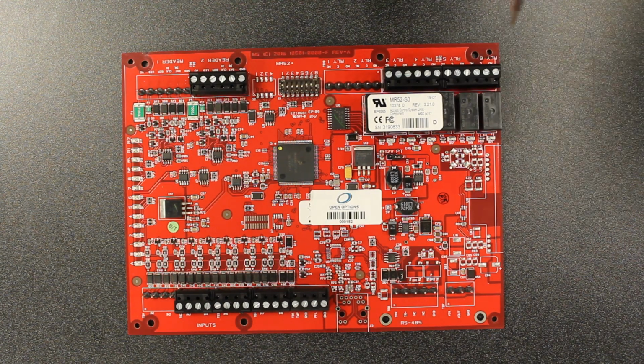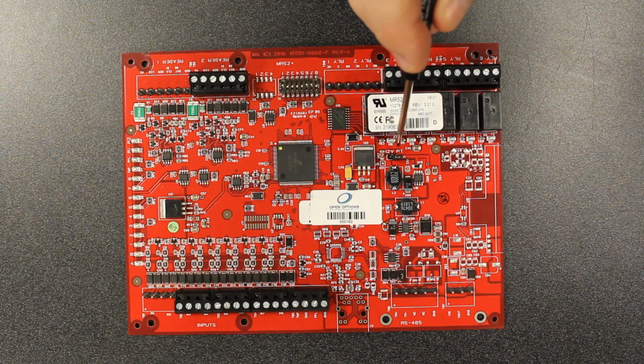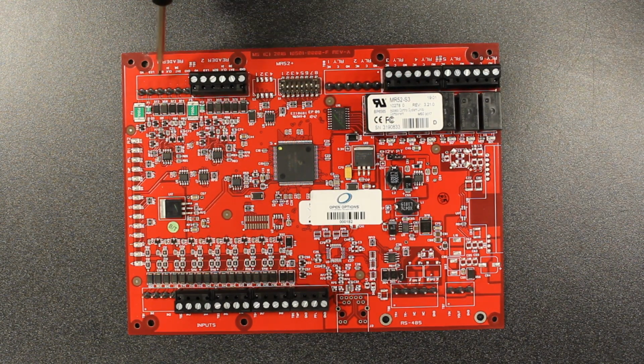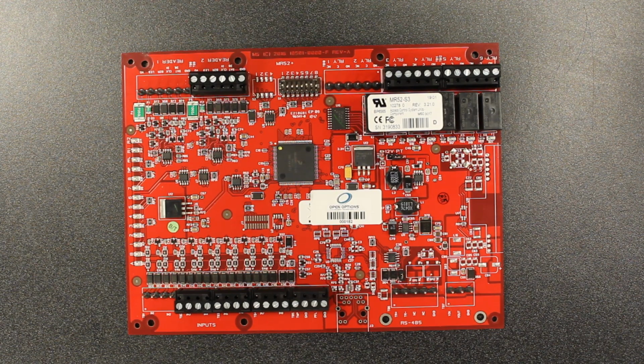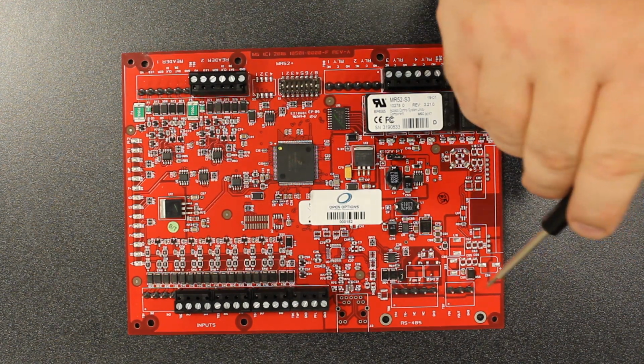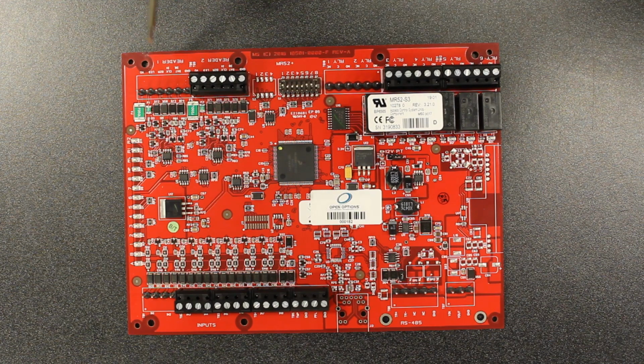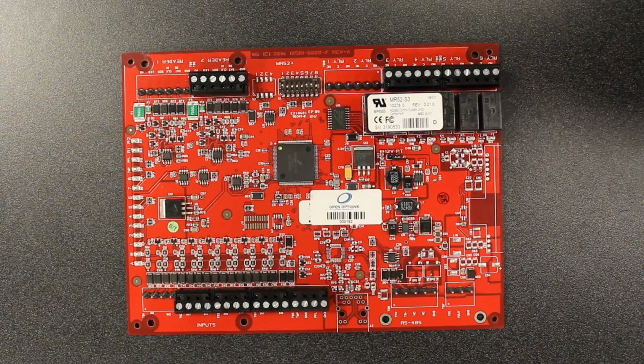It's important to know that in advance, so I can set my jumper to pass through so that when I put my 12 volt reader on, it gets the 12 volts. If you're powering at 24 volt and you set it to pass through, you hook up a 12 volt reader, you're gonna let the magic smoke out. Don't do that.